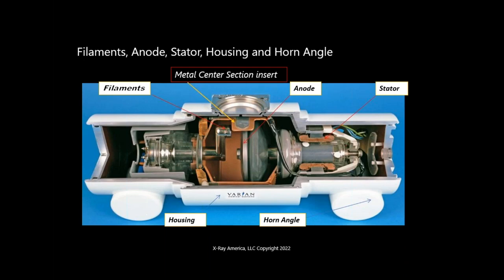Yeah, that's absolutely right. And with anode ground too, because it goes to ground, you don't need the dielectric aspects of the oil. It's really just for cooling. Sometimes, for instance, the Canon tubes, they use glycol. More questions?